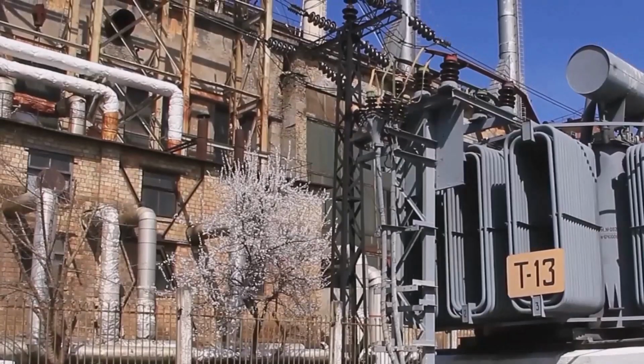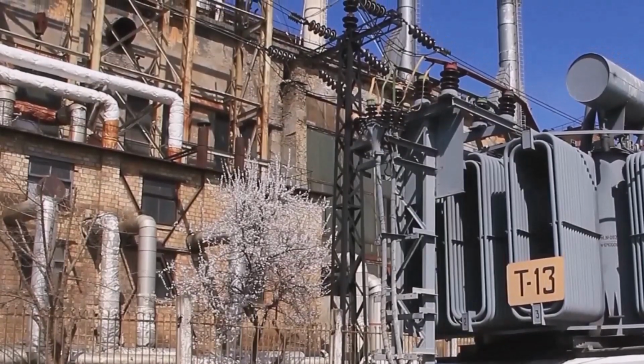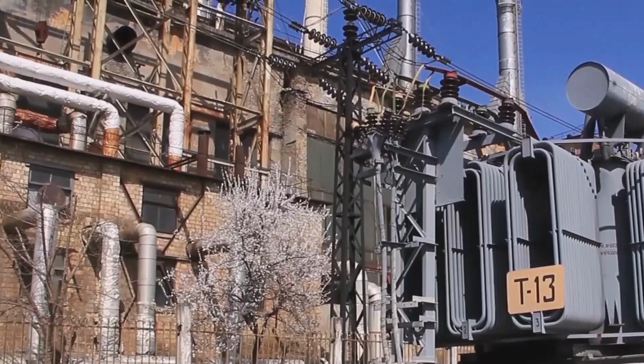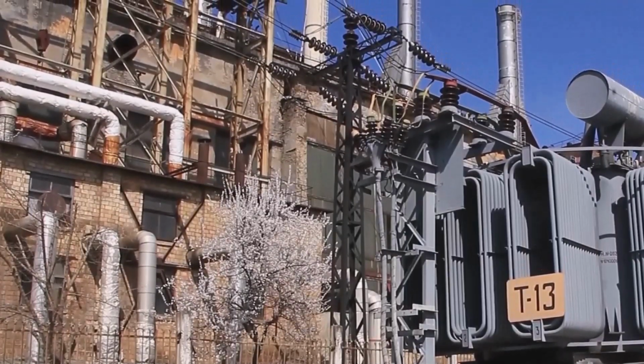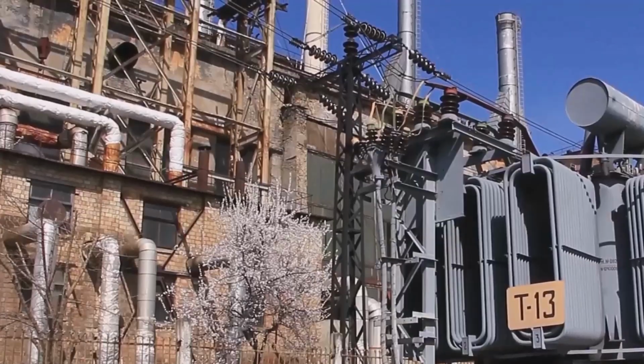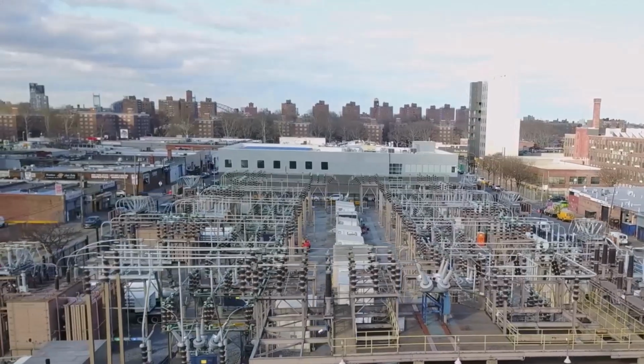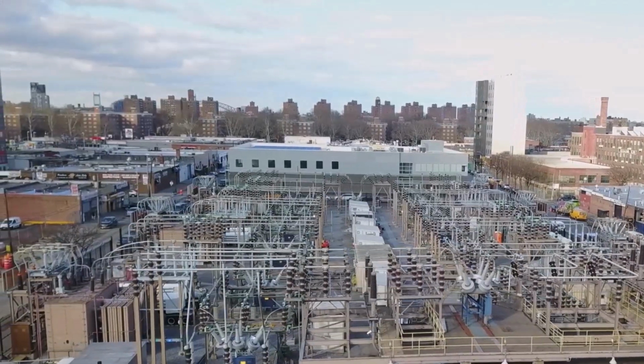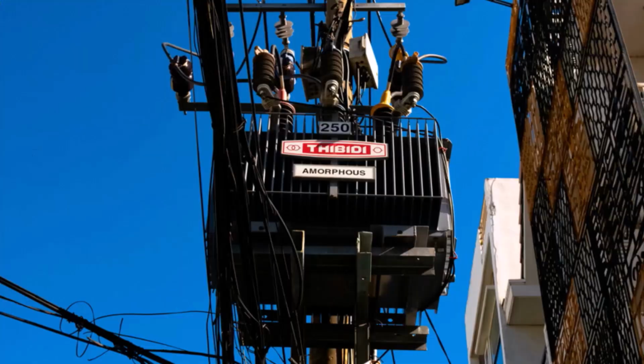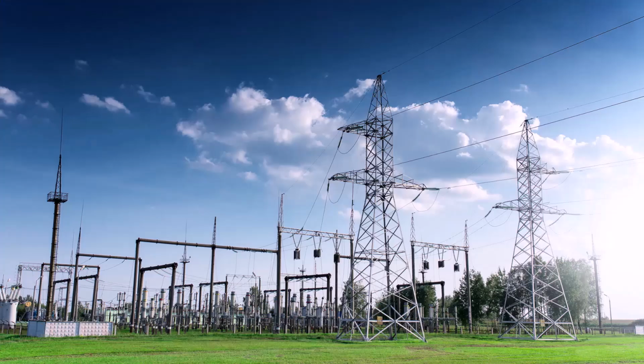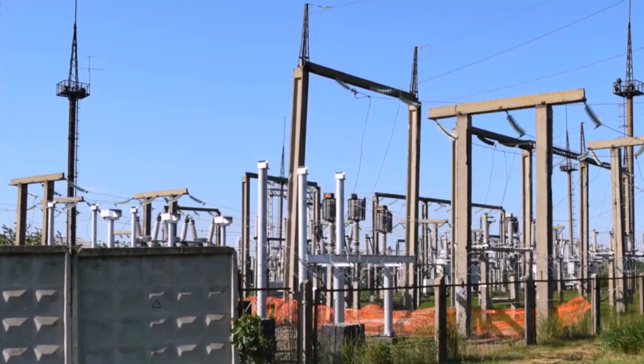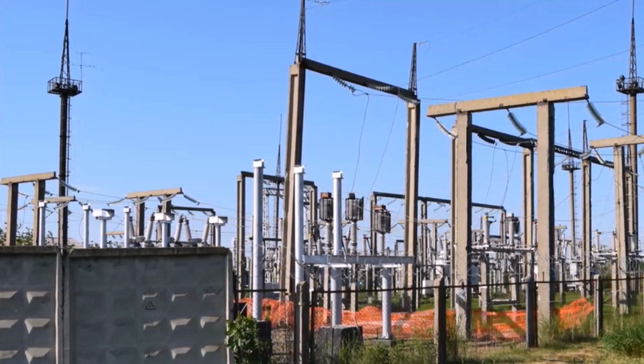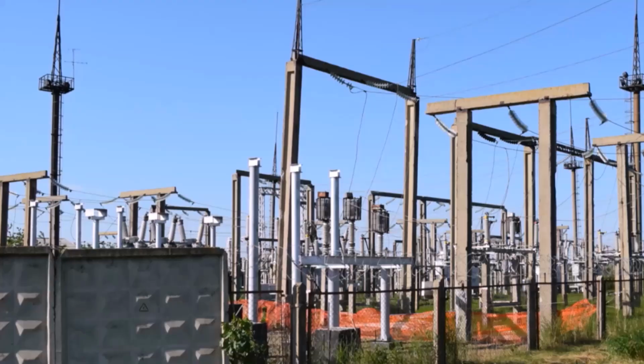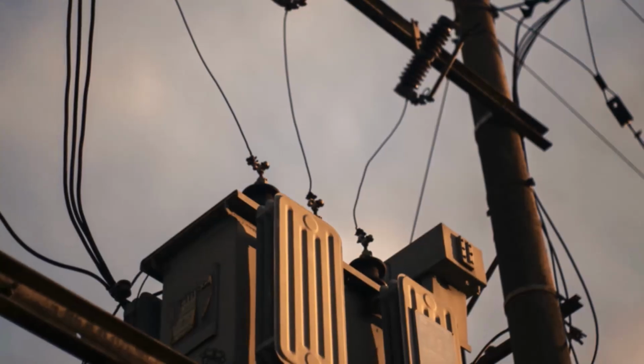This setup allows the utility company to deliver high-voltage power efficiently over distances, and then easily tap into it to provide the single-phase power that our homes use. It's the standard for residential and commercial power distribution because of its safety and flexibility. Transformers are another place where Y connections are essential. A transformer is a device that changes the voltage of electricity up or down, and its internal coils, or windings, can be connected in several ways. The Y connection is a very popular choice for these windings.